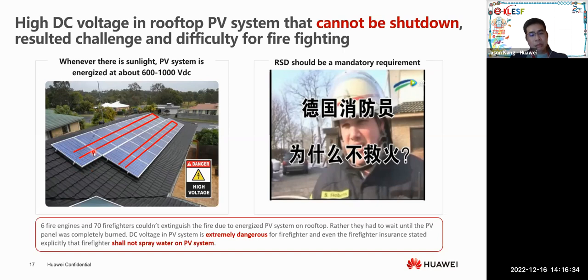So if there's an issue on the rooftop, any fault, the inverter will trip, right? The inverter will trip, meaning there's no AC output. But then again, the sun is still there, the irradiance is still there. The irradiance will penetrate the PV modules and still produce DC power. So whatever power is connecting to the inverter, before the inverter, there will still be DC power, even though there's no AC output. That's the problem there.